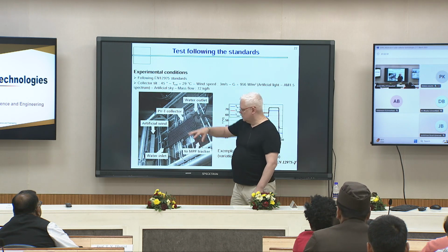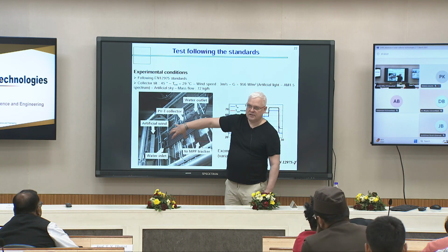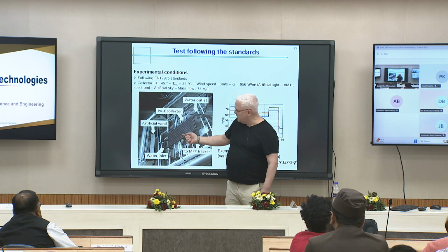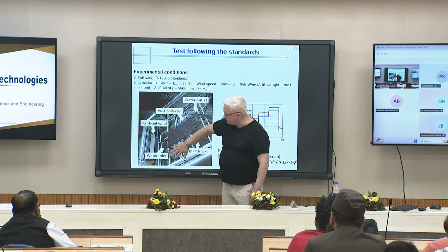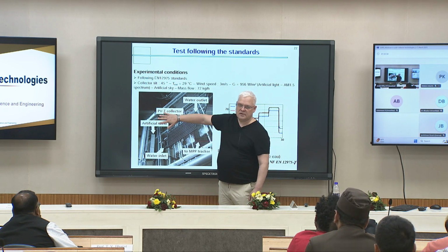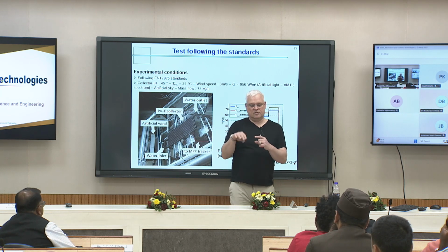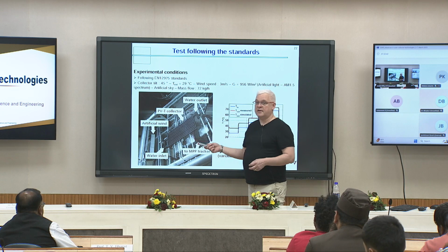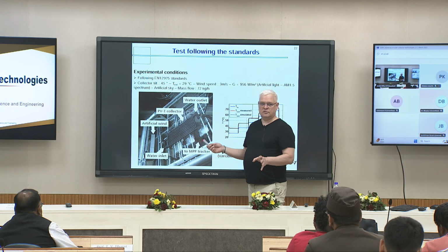Okay? So you have radiation coming from the artificial light, absorbed by the solar collector and so on, and the solar collector emits in the direction of a cool surface, which is this glass, inside which there is a cool airflow. It is the condition to have a quite accurate evaluation of the efficiency of a solar thermal collector in controlled conditions.